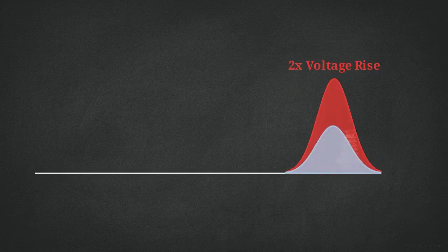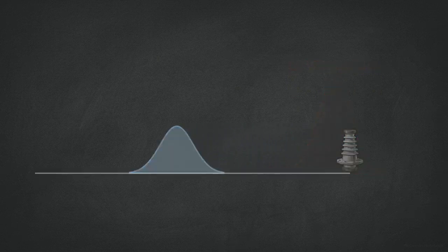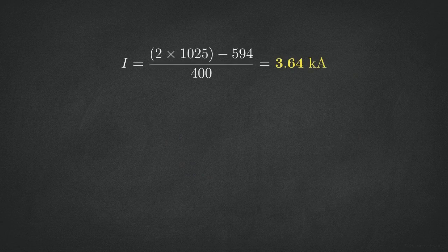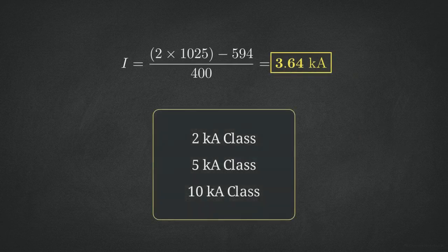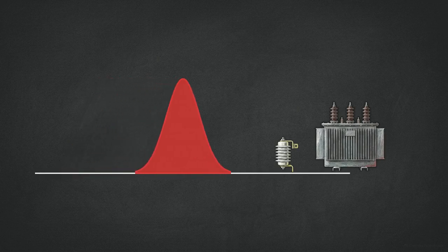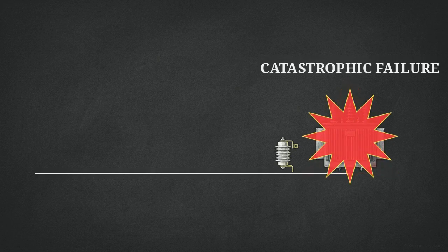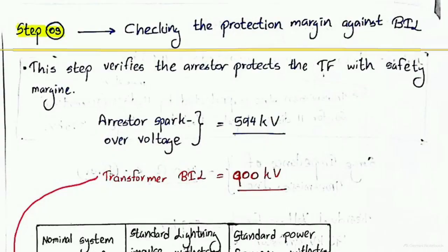Here is the physics of why we double that number. When an electrical surge travels down a line and hits a high impedance point, like an open-circuited transformer, it behaves like a physical wave hitting a concrete wall. It reflects backward and stacks directly on top of itself, doubling the voltage at the point of impact. Factoring in that reflection gives us a discharge current of 3.64 kiloamps, leading us to select a standard 5 kiloamp class arrestor. Without accounting for wave reflection, the resulting design would be unable to handle the actual voltage rise at the transformer terminals.